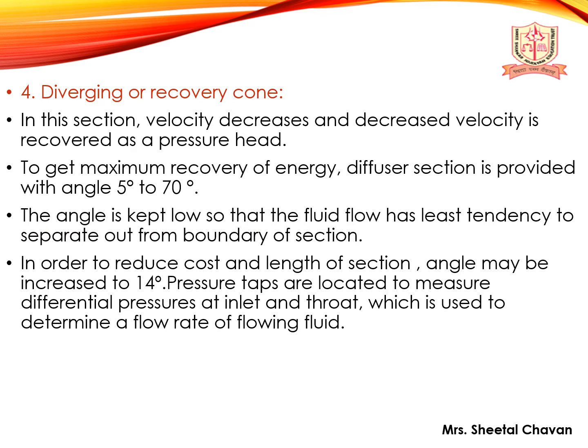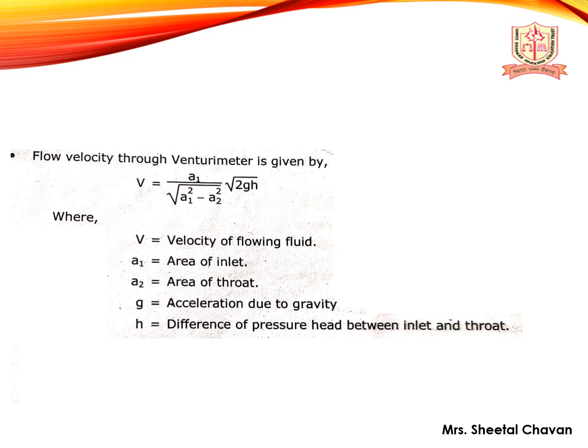The fourth section is the diverging or recovering cone, where velocity decreases and the decreased velocity is recovered as pressure head. The diffuser section has an angle of 5 to 7 degrees to minimize flow separation, though it may be increased to 14 degrees to reduce cost and length. Pressure taps at the inlet and throat measure the differential pressure to determine the flow rate. The flow velocity through the venturimeter is given by: V = (a1 / √(a1² − a2²)) × √(2gh), where V is velocity, a1 is inlet area, a2 is throat area, g is acceleration due to gravity, and h is the pressure head difference between inlet and throat.